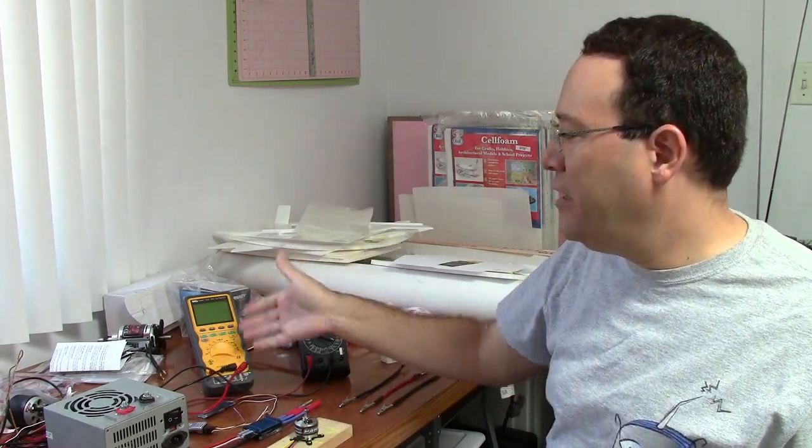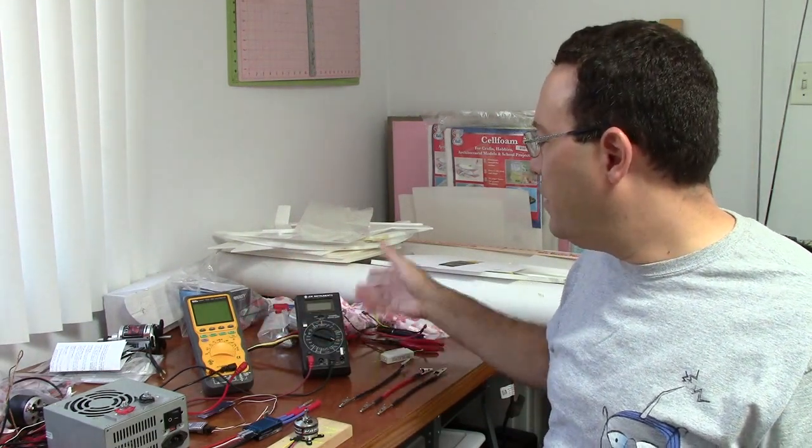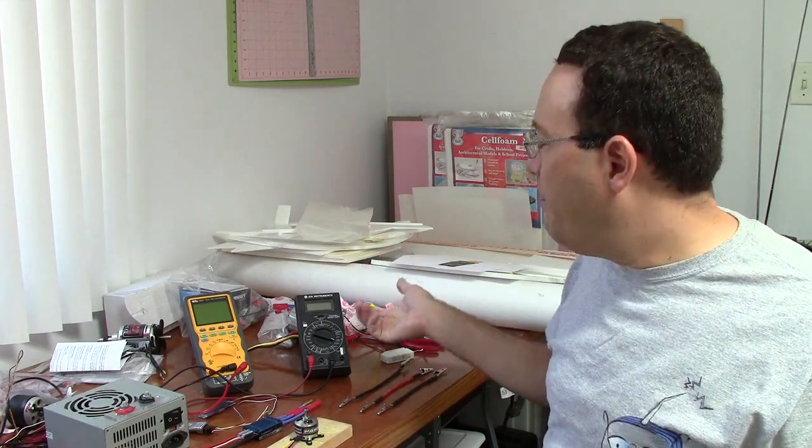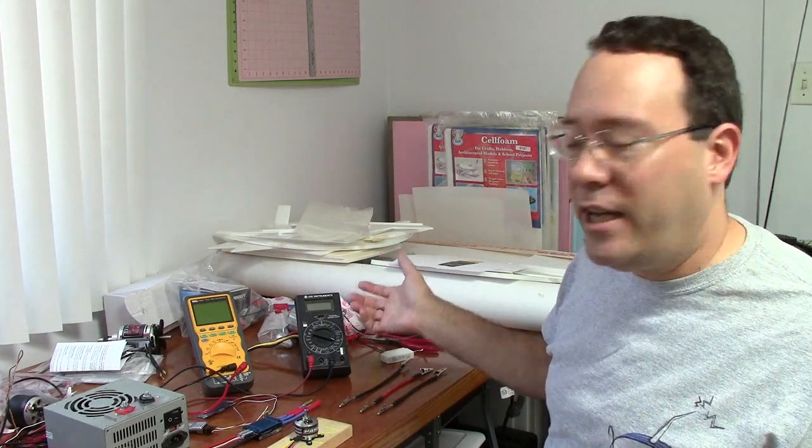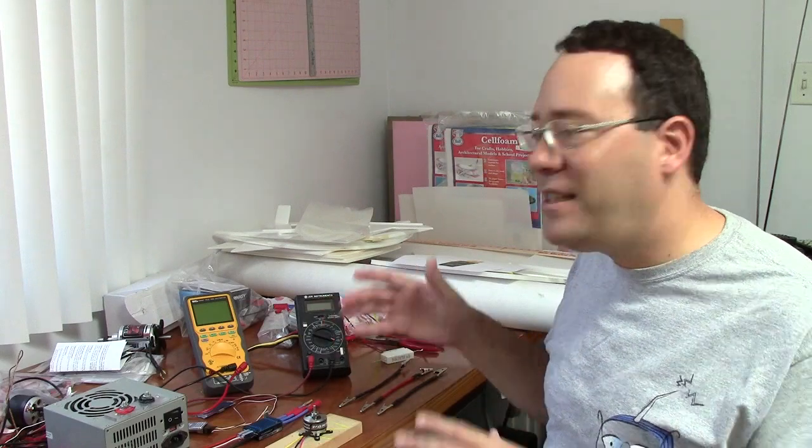But again, this is a $350 multimeter. This meter, which is about $50, it's not an RMS multimeter. So if you take a measurement of an AC circuit, which is what the motor is, it'll be very inaccurate and you probably won't even know about that. So that's the first caveat.